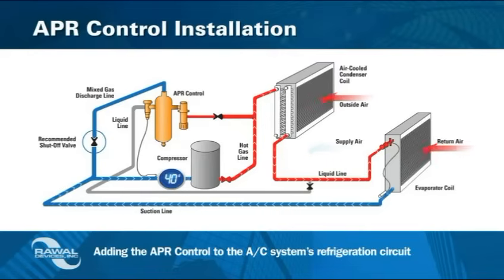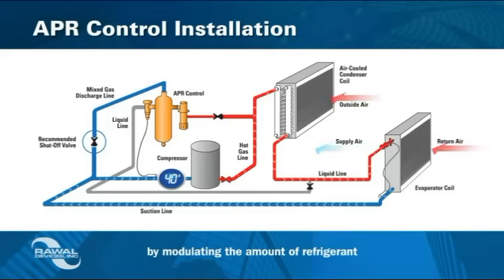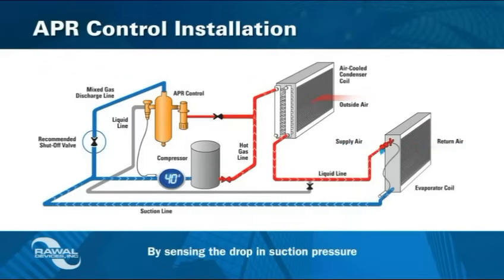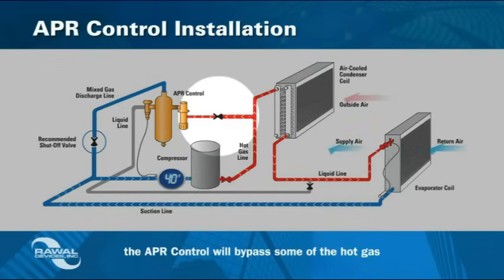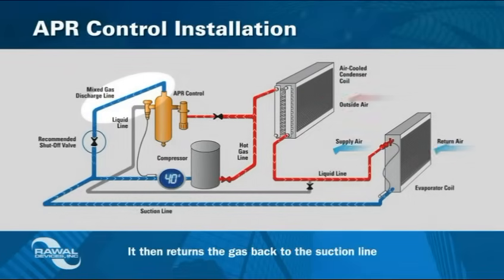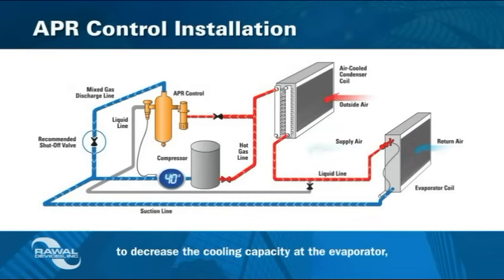Adding the APR Control to the AC system's refrigeration circuit will extend run time and moisture removal by modulating the amount of refrigerant that is sent to the evaporator coil. By sensing the drop in suction pressure caused by decreasing return air temperature, the APR Control will bypass some of the hot gas through a de-superheat chamber. It then returns the gas back to the suction line to decrease the cooling capacity at the evaporator, thus extending the run time.